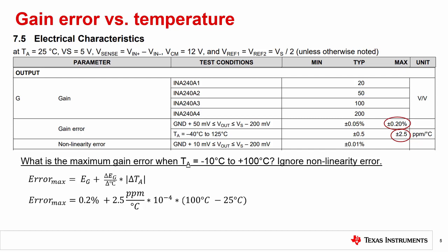Only the largest absolute change from 25 degrees Celsius should be considered because the gain error specification can almost always be positive or negative. Note that an easy way to convert parts per million into percentage is to multiply by 10 to the negative fourth power. So, if we continue with the calculation in terms of percent, the maximum gain error is plus or minus 0.21875%.